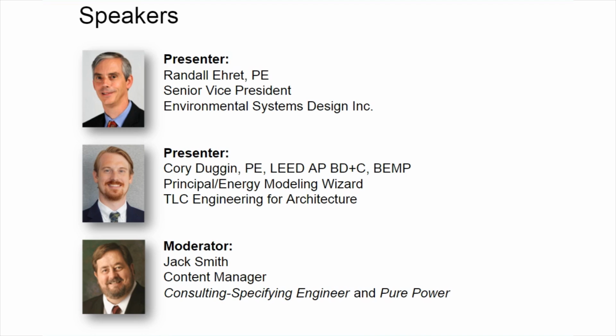Article 701 covers our legally required standby systems, which are the less critical loads, as we discussed earlier. Things like smoke management systems or building pressurization systems, things that are important to have running in an outage event, but not necessarily directly related to life safety. And then Article 702, which covers optional standby systems, are the systems that you just elect as an owner or an engineer to put on emergency power, but are not required by code. Hope that helps, Jack.